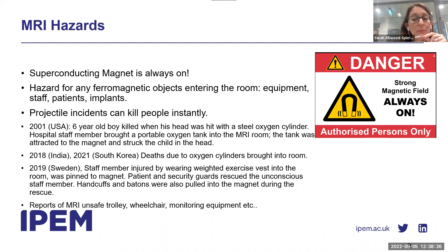And for each of these incidents that results in serious injury or death and that makes the papers, there will be numerous reports of an MRI unsafe trolley, the wrong wheelchair, the wrong monitoring equipment brought into the room. And it's often just a case of luck that it didn't result in more serious injury. So this hazard is present all the time. Consider in radiotherapy, for example, the use of carbogen cylinders. That may be a similar risk to your oxygen cylinders. Is there a clear procedure for where these are placed and how they are used?